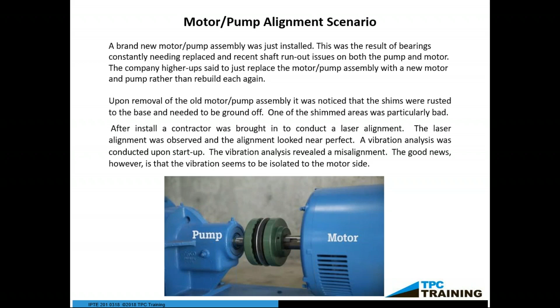Upon removal of this pump assembly, it was noticed the shims on the base, which are usually loose, were not put in properly, and one of these shims particularly had a problem. After installing, a contractor was brought in to conduct a laser alignment. When he did this, vibration analysis was done, and they realized it was misaligned because of the coupling. The type of coupling used gives a little bit of space to play with, but it might not be the right coupling. That's why if something's failing constantly, you think about doing a root cause analysis and why it's happening.